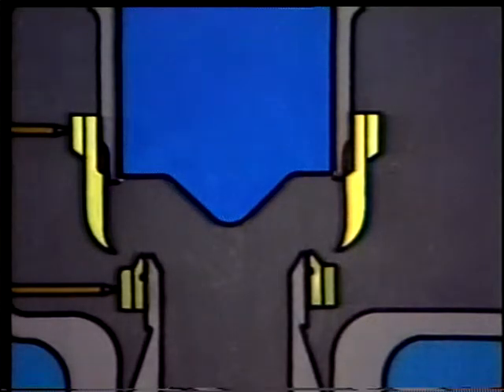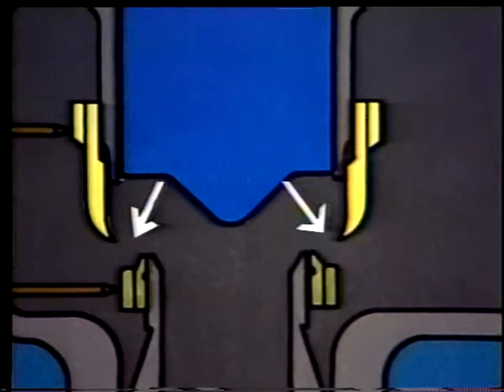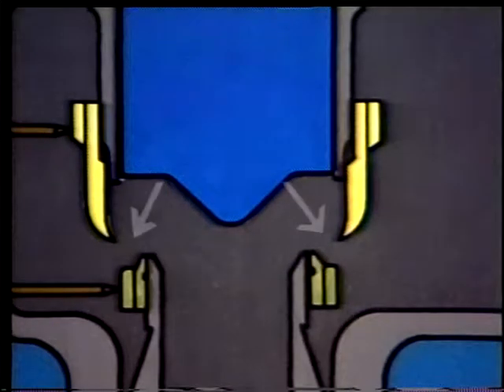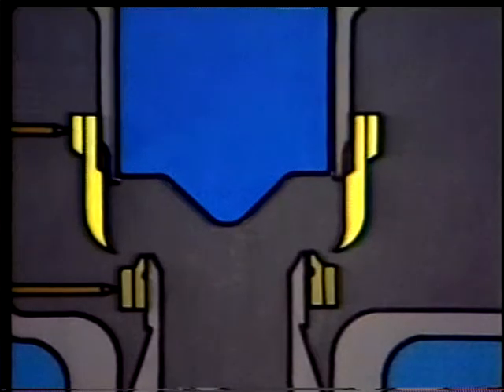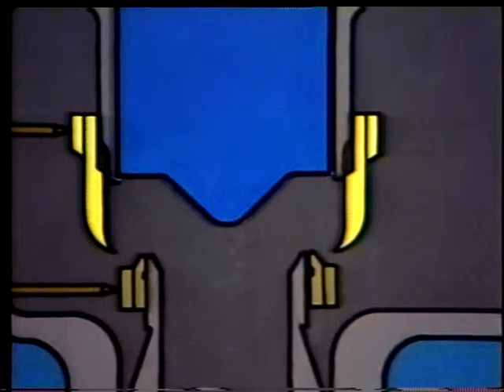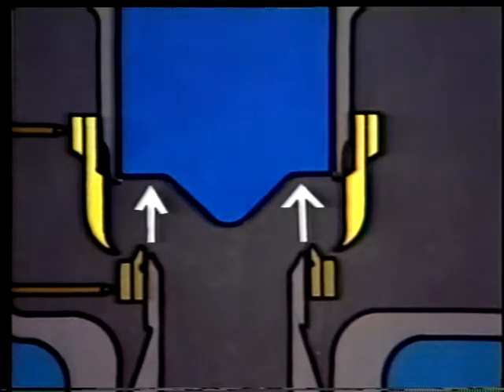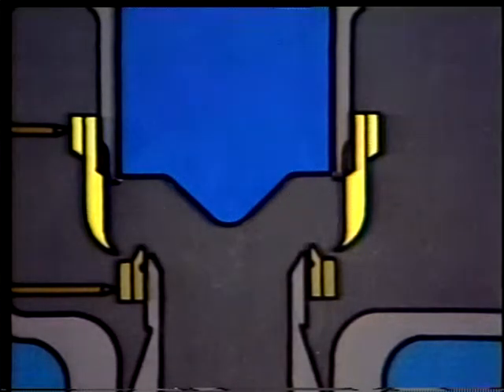Adjustment of the rings is the same for nozzle reaction valves as for two-ring huddling chamber valves. Raising the guide ring widens the escape path for the steam, decreasing the blowdown. Lowering the guide ring narrows the escape path, increasing lifting force and blowdown. Raising the lower ring directs more steam against the disc, which can lead to prolonged simmering if the ring is adjusted too high.